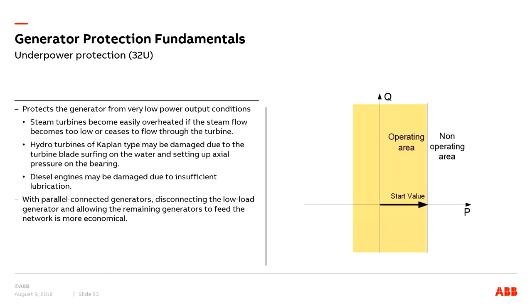Steam turbines can easily become overheated if the steam flow becomes too low or ceases to flow through the turbine. And with parallel connected generators, disconnecting the low load generator and allowing the remaining generators to feed the network is more economical. So we need to detect a generator which is delivering underpower, and then be able to isolate it from the system.